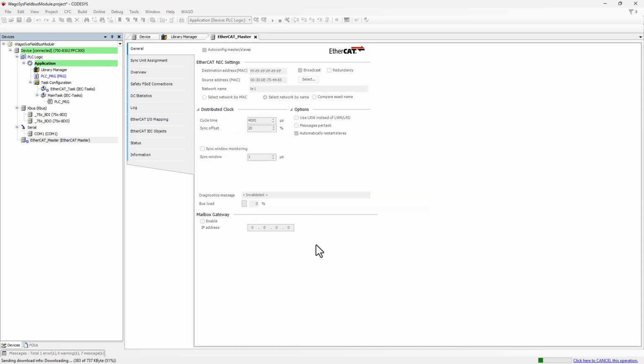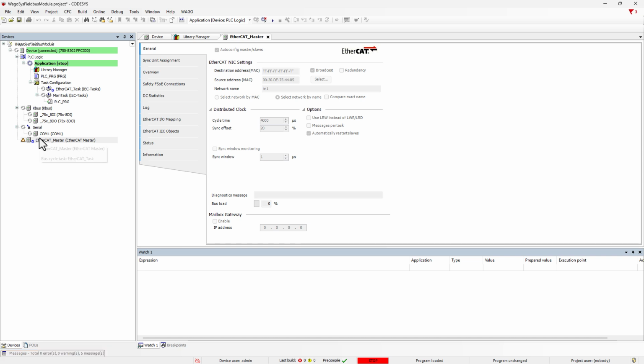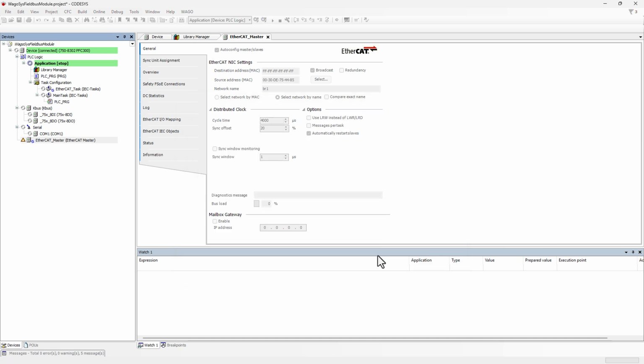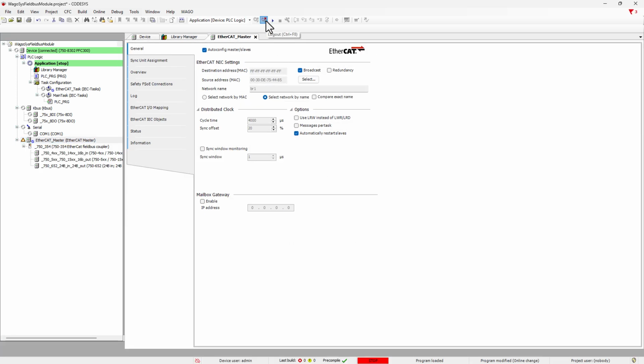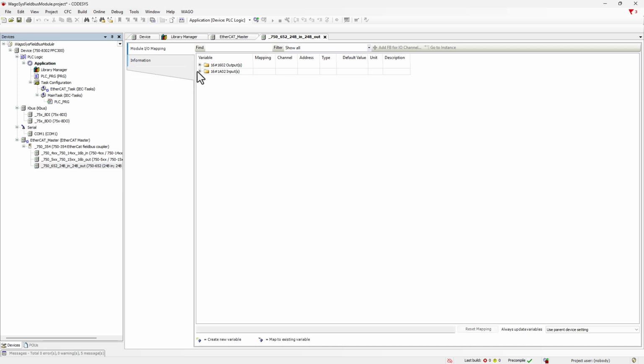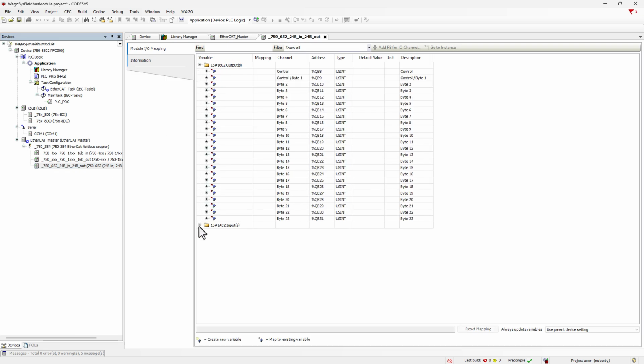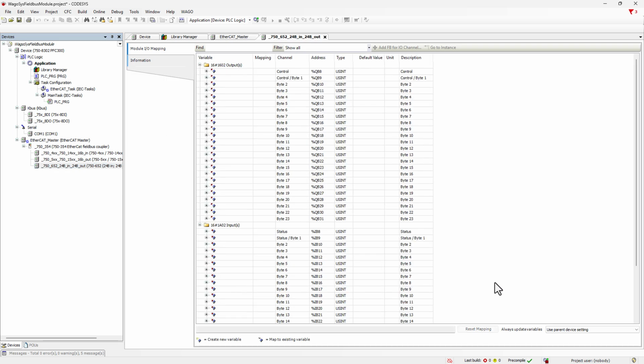After loading the program onto the controller, the EtherCAT master can search for connected devices. In addition to the digital I/Os, the serial interface is also detected. If we expand this item, we can see, because EtherCAT transmits data byte-wise, the 24 input bytes and 24 output bytes. With digital I/Os, this would be straightforward. Map variables and you're done. For the serial interface, however, it's not that simple.